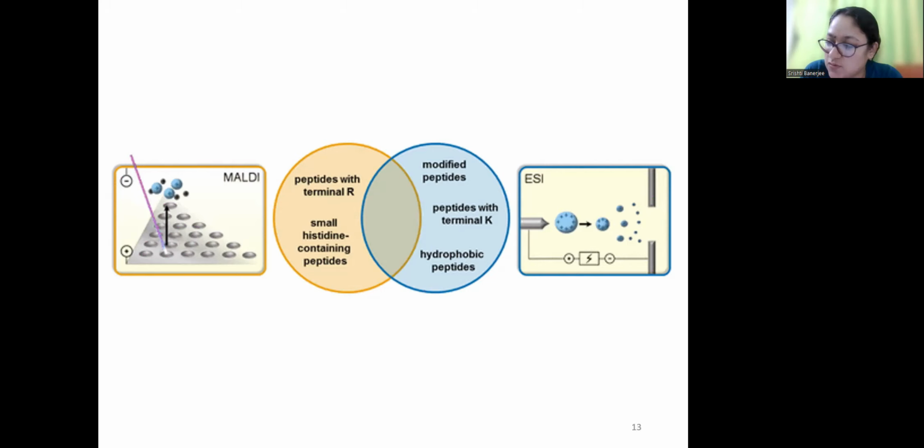Now, one method is known as ESI, or electrospray ionization. What is done here is that sample molecules are first sprayed in an electric field to produce ions. You mix your sample with a solvent, which could be methanol, acetic acid, acetonitrile, ammonium hydroxide, and also water. Depending on the pH of the solution, the molecules will have either a positive or a negative charge. Then you spray it. The solution has your charged samples. Now you spray it through a syringe.